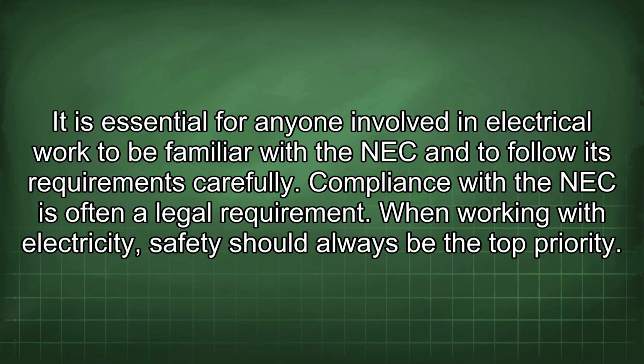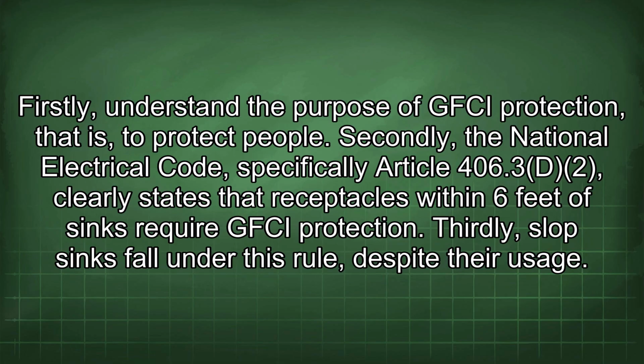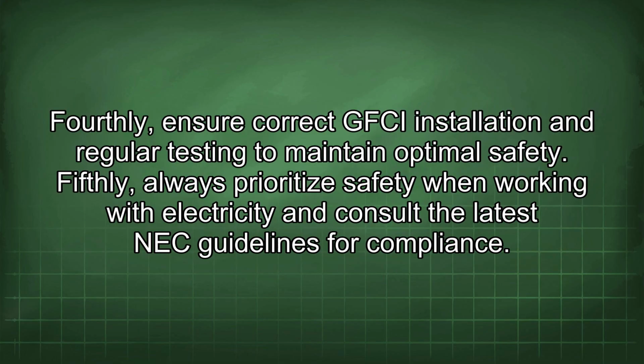It is essential for anyone involved in electrical work to be familiar with the NEC and to follow its requirements carefully. Compliance with the NEC is often a legal requirement. When working with electricity, safety should always be the top priority. Firstly, understand the purpose of GFCI protection, that is, to protect people. Secondly, the National Electrical Code, specifically Article 406.3(D)(2), clearly states that receptacles within 6 feet of sinks require GFCI protection. Thirdly, slop sinks fall under this rule, despite their usage. Fourthly, ensure correct GFCI installation and regular testing to maintain optimal safety. Fifthly, always prioritize safety when working with electricity and consult the latest NEC guidelines for compliance.